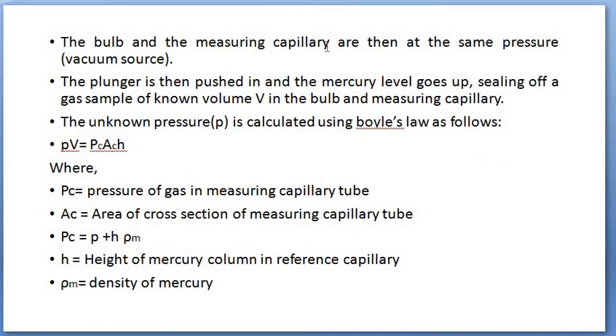The bulb and the measuring capillary are then at the same pressure, because of the vacuum source. The plunger is then pushed in. All this time we had released it to first reduce that level. Now the plunger is pushed in and the mercury level goes up, sealing off a gas sample of known volume V in the bulb and the measuring capillary.